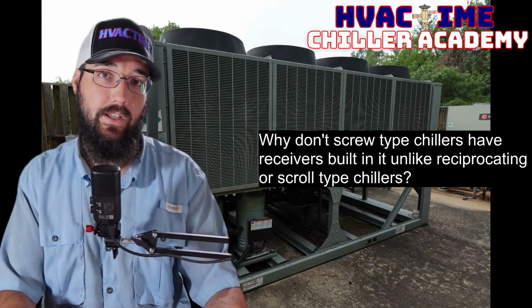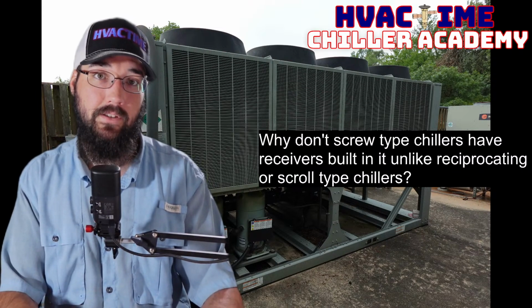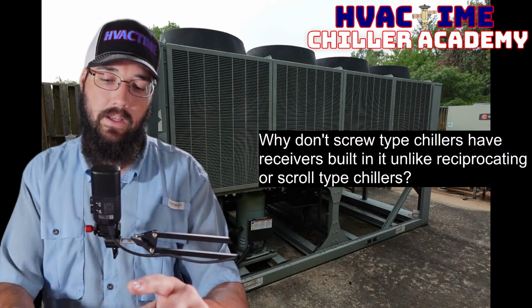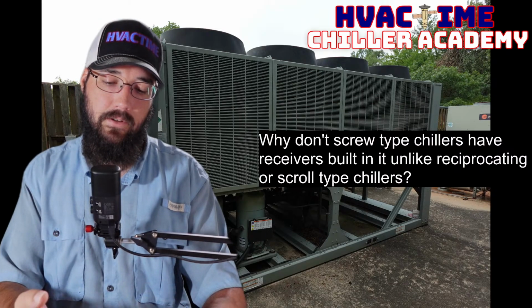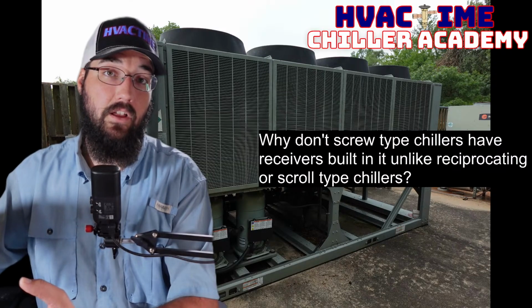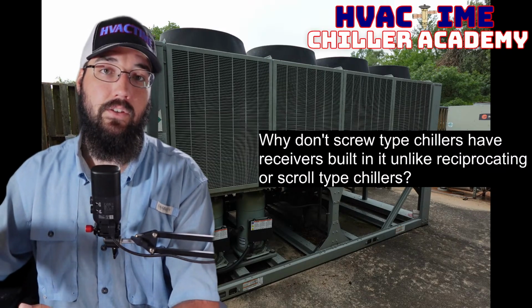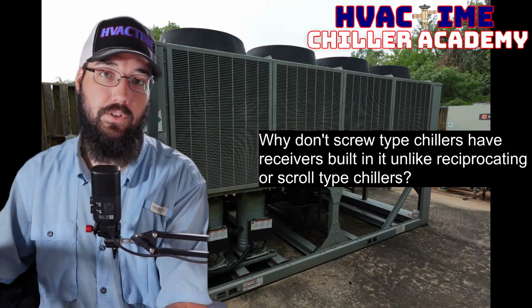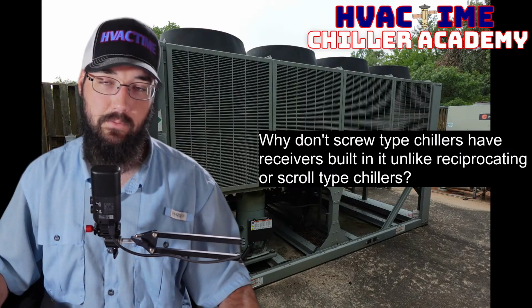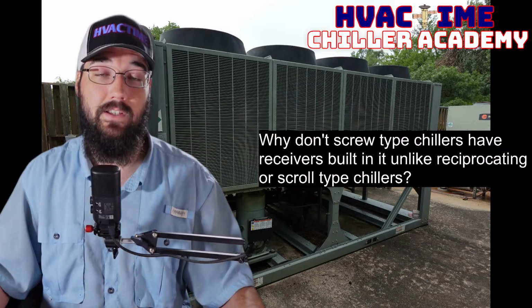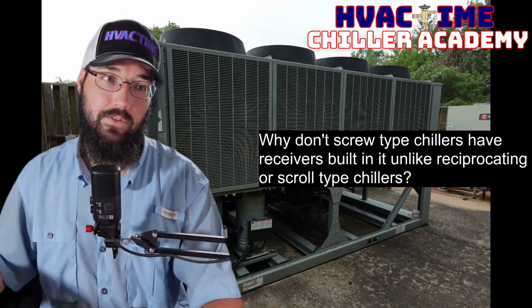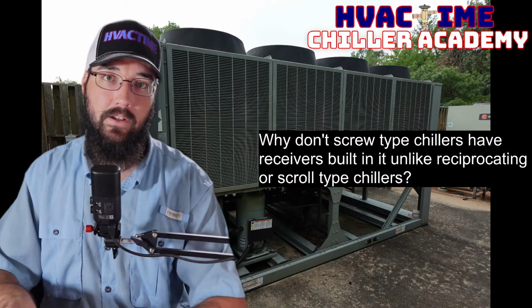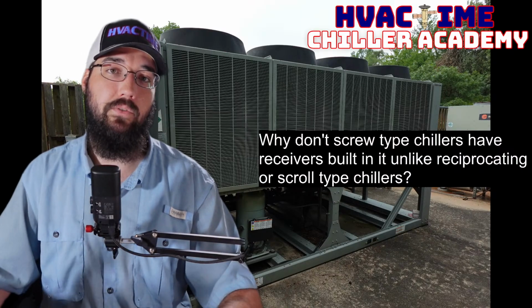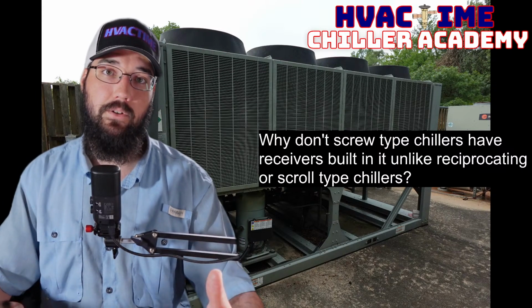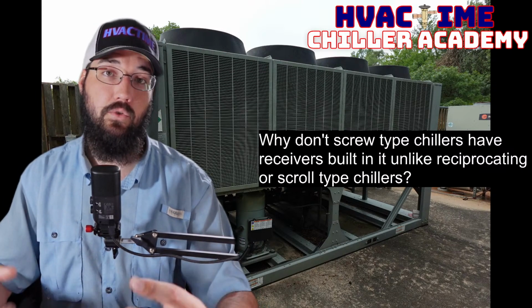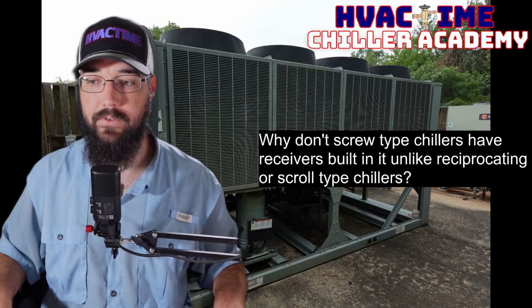Is it going to have to sit in a very unloaded state for an extended period of time, just barely kind of cruising, and then have to scale up very heavily, very fast to capture the load situation? You know, I'd say a CT machine especially might be a prime example of that, or a CNC machine at that. We may not want to shut the chiller down, so we'll let it ride at a minimal load for a while, but then once we fire up an operation, we need to be able to capture all of that electronic load quickly to maintain a stable temperature.